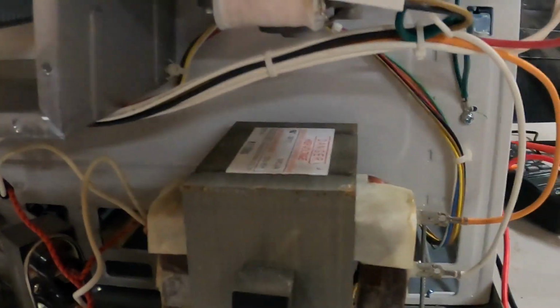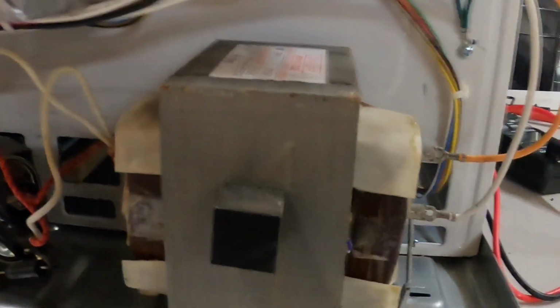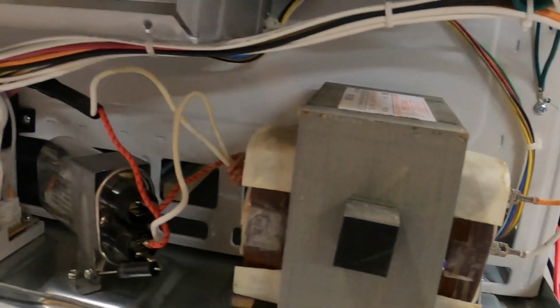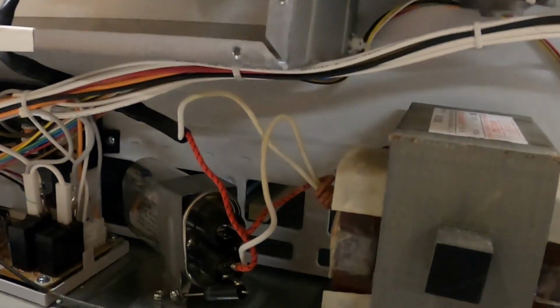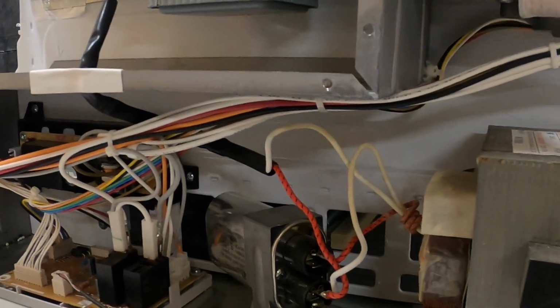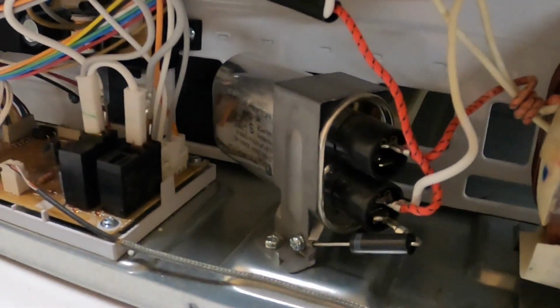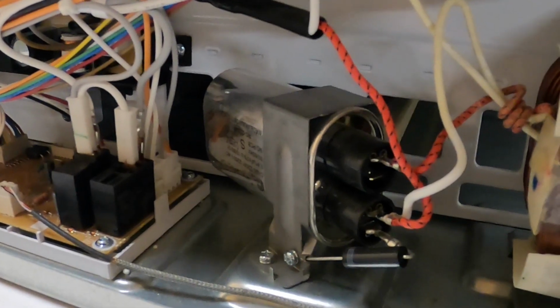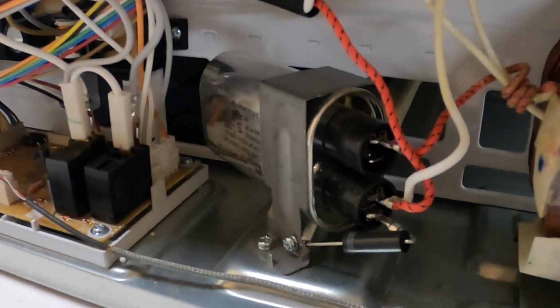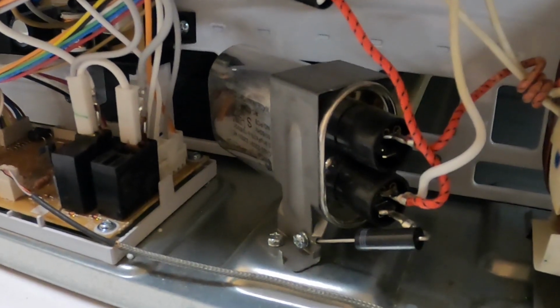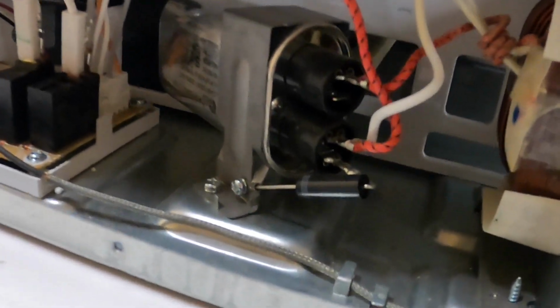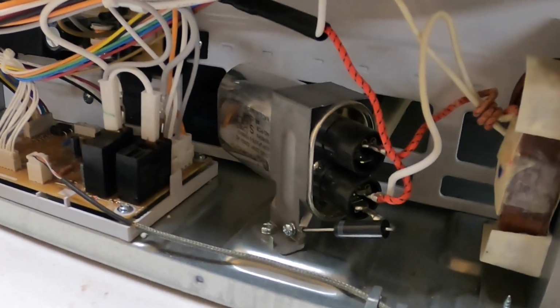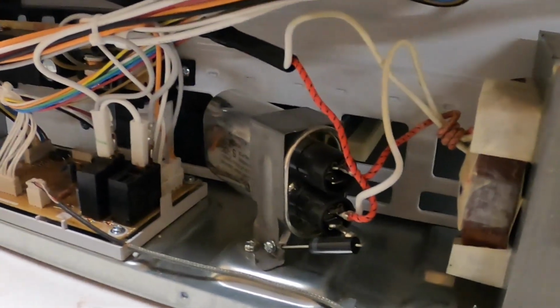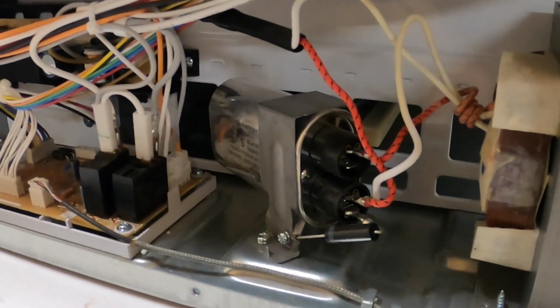Now, we're going to get into no heat, but before we do that, this is where safety becomes really important on microwaves. Right here we have what's called your high voltage capacitor. That's that big long silver thing that's oval shaped. It stores between 2,000 and 3,000 volts, and it is very painful if you discharge it through your body.